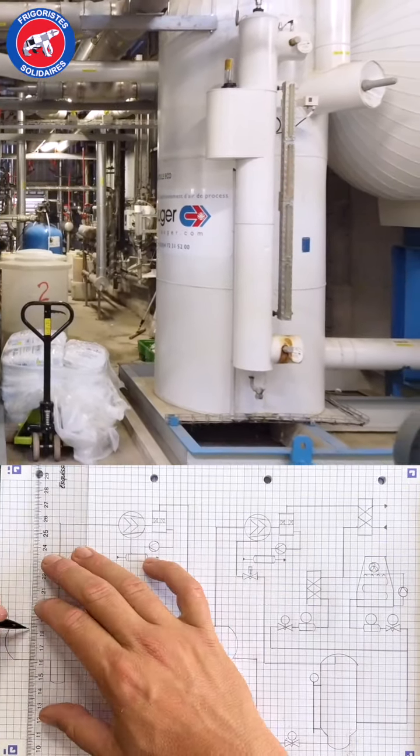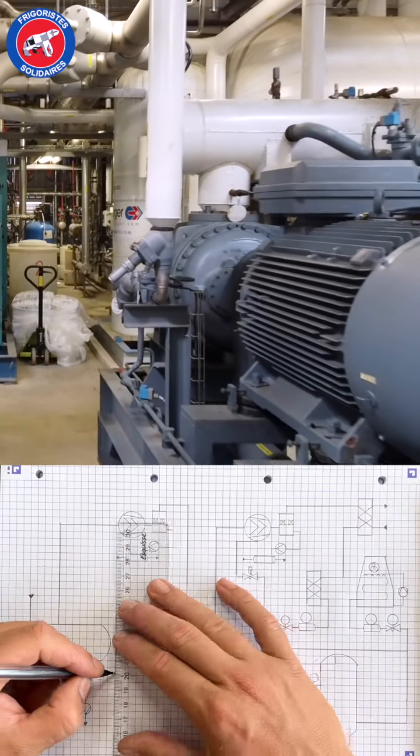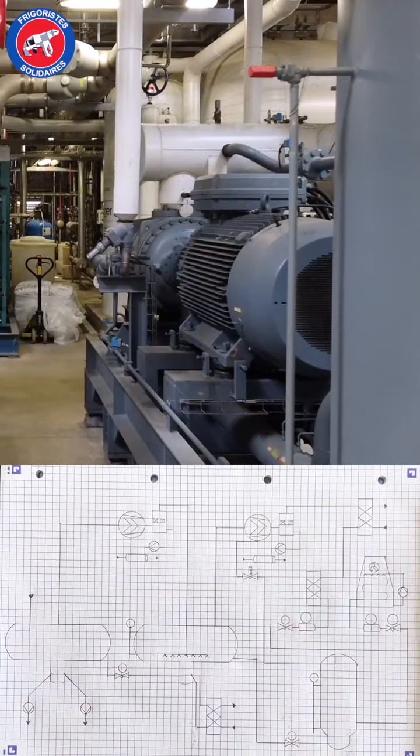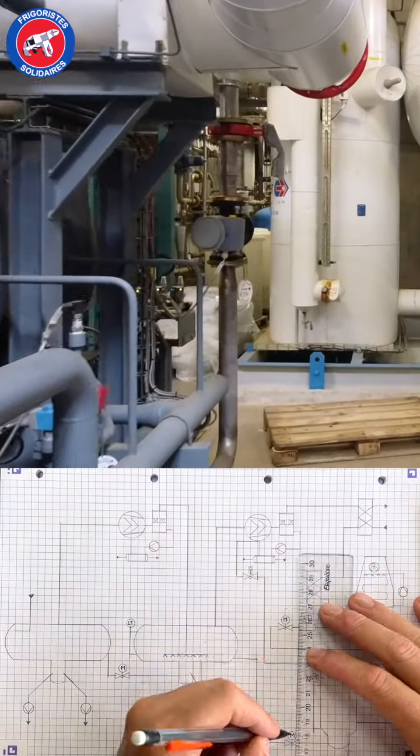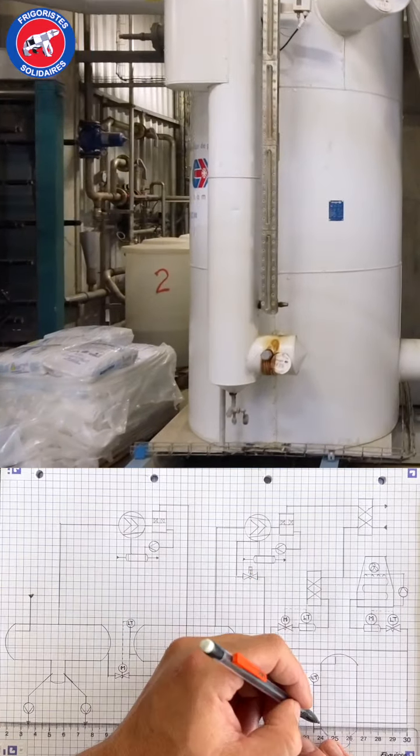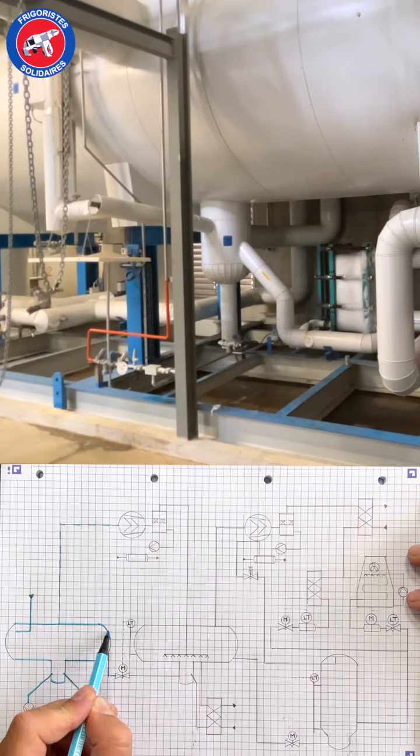The expanded fluid goes into the economizer receiver to supply the medium pressure compressors with vapor at zero degrees C. A level sensor controls motorized valve which sends the liquid to the medium pressure liquid separator.